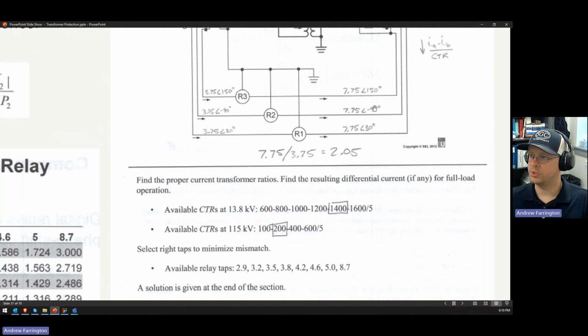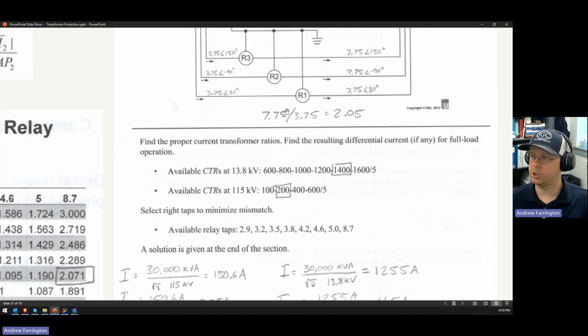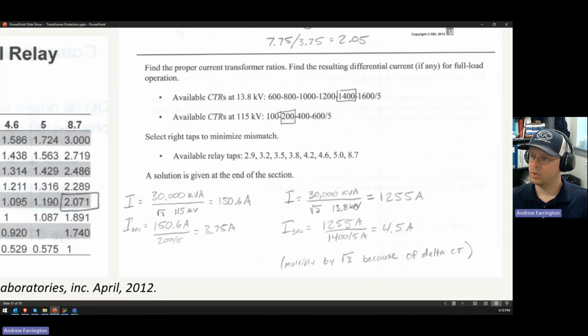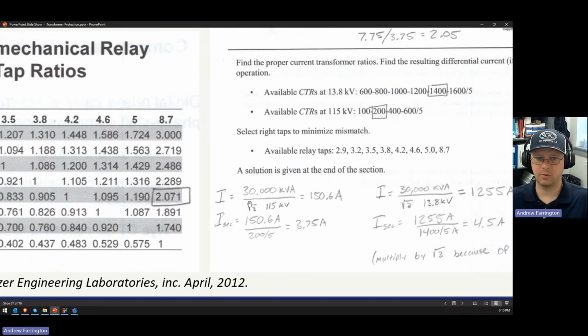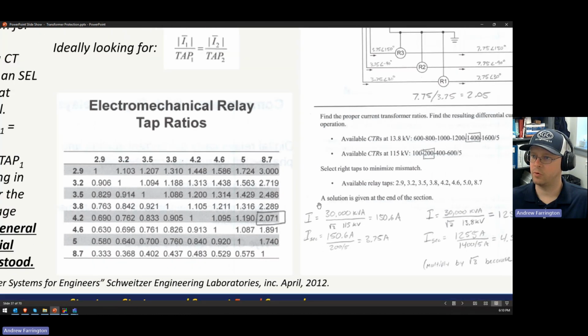So once you get that, then you can see that the currents into the relay in this example again is 3.75 amps coming from the high side and 7.75 amps coming from the low side. And the ratio of the low side current to the high side current is about 2.05. Okay, and again, all of that's written here. Should be a very good example for you to follow for your homework problem.